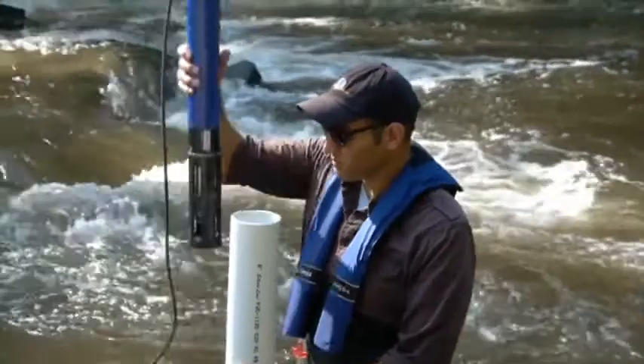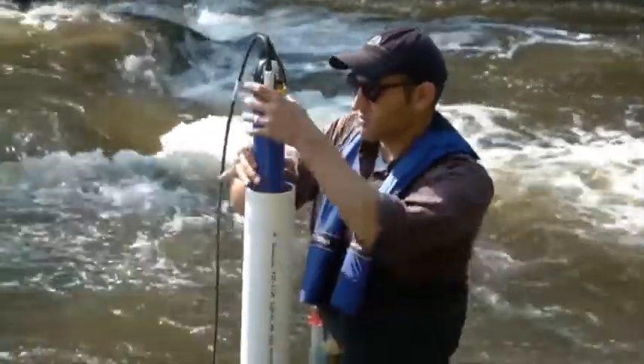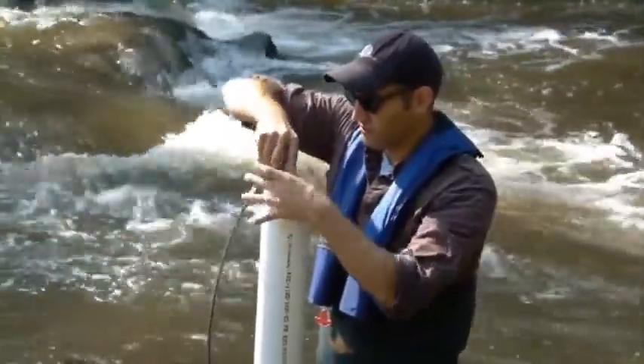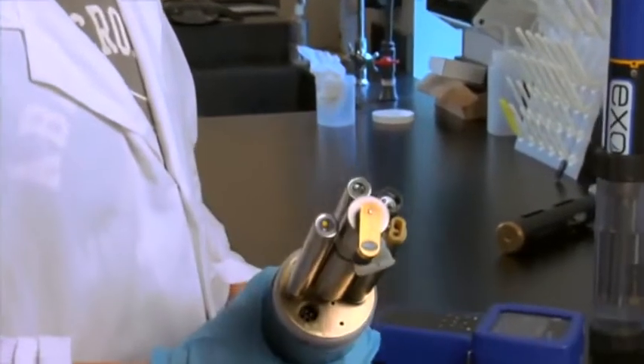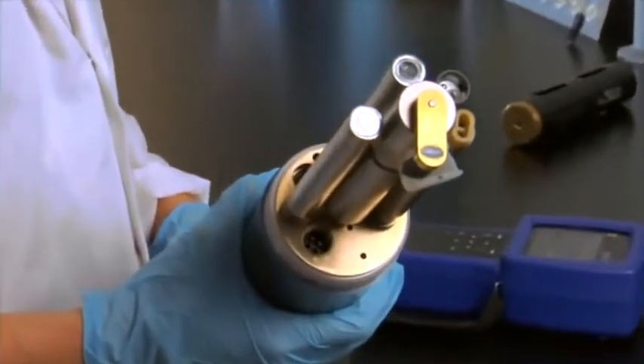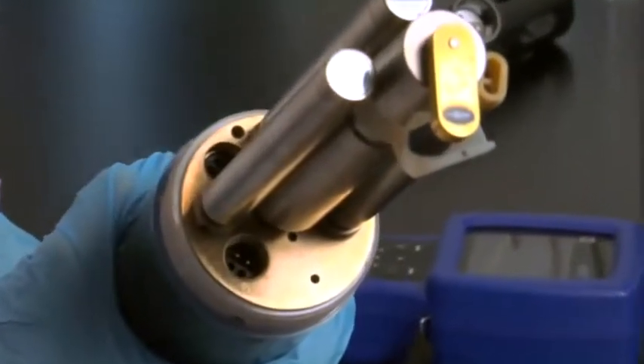I'm Rob Ellison, and I'm excited to introduce you to YSI's new EXO platform. EXO was designed to be extremely versatile, allowing you to configure a sonde for different applications in minutes. The key to this versatility is the smart sensors and smart ports. Each smart port is identical and accepts any EXO sensor, so sensor payloads are up to you. Also, each smart port uses a power monitoring system that continuously monitors power draw and will shut down a port automatically if a problem is detected, thus protecting the rest of the system.